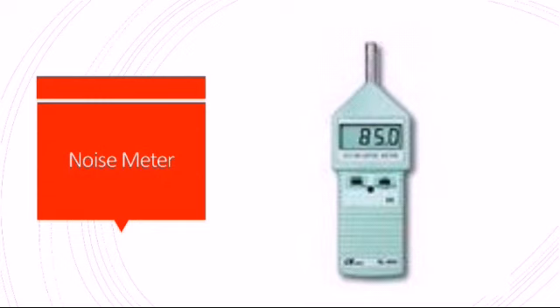The diaphragm of the microphone responds to changes in air pressure caused by sound waves. That is why the instrument is sometimes referred to as a sound pressure level, SPL, meter. This movement of the diaphragm, i.e. the sound pressure deviation, Pascal (Pa), is converted into an electrical signal, volts (V).